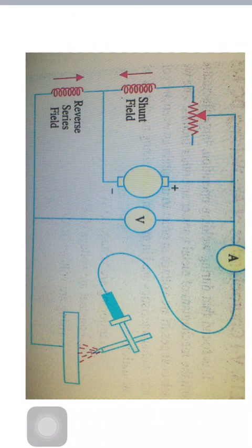With the help of the shunt field, generator voltage and current values can be adjusted to the desired values, and matters are arranged such that despite changes in arc voltage due to variations in arc length, the current remains practically constant.